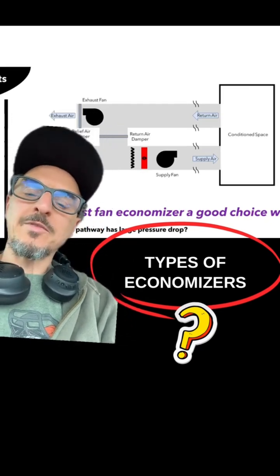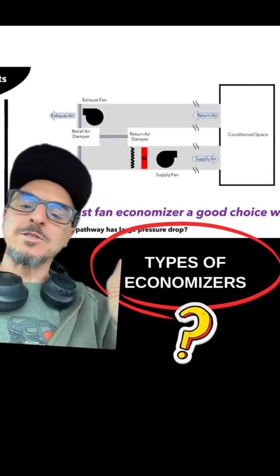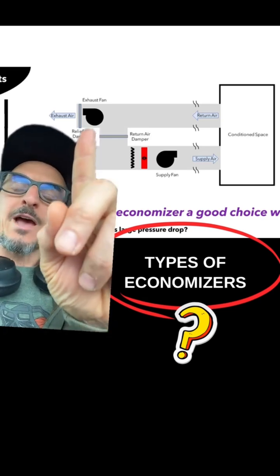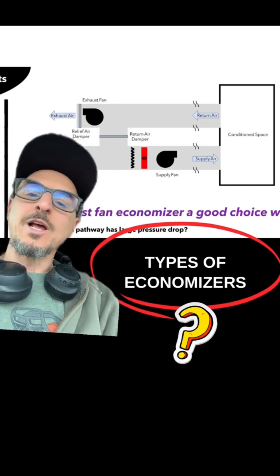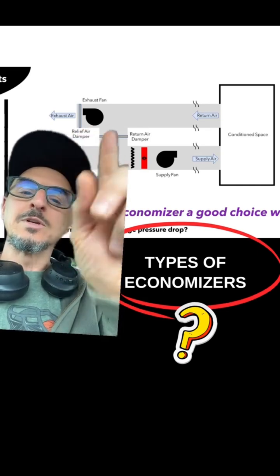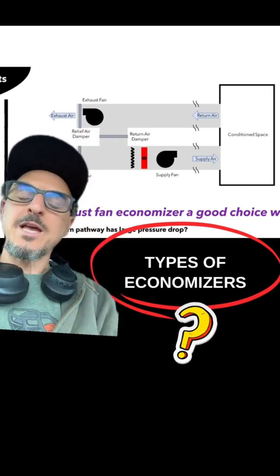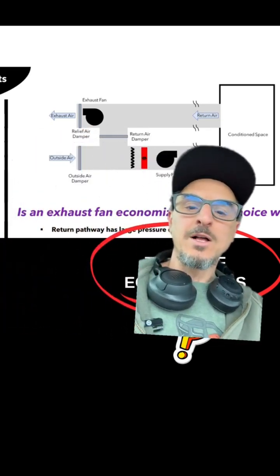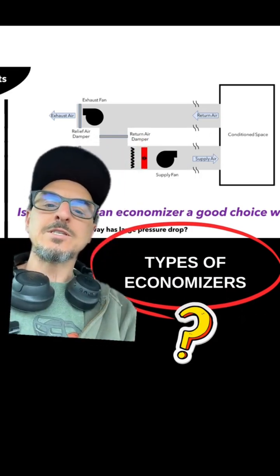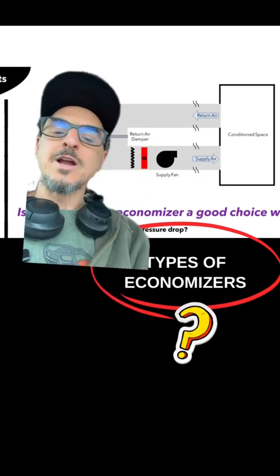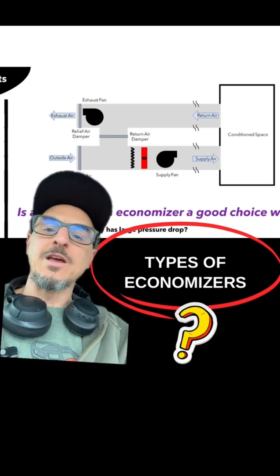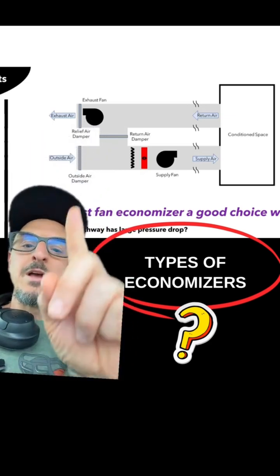The next type is an exhaust fan economizer, where you actually have an exhaust fan. During economizer mode, you turn this fan on, which helps to relieve the pressure of the space. This works well if you have over one inch of static in the return air duct — so one inch of static. This is very common in a VAV system.